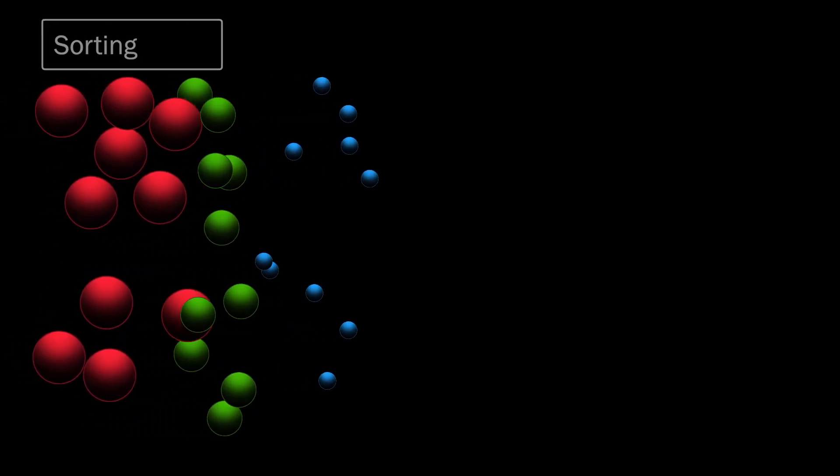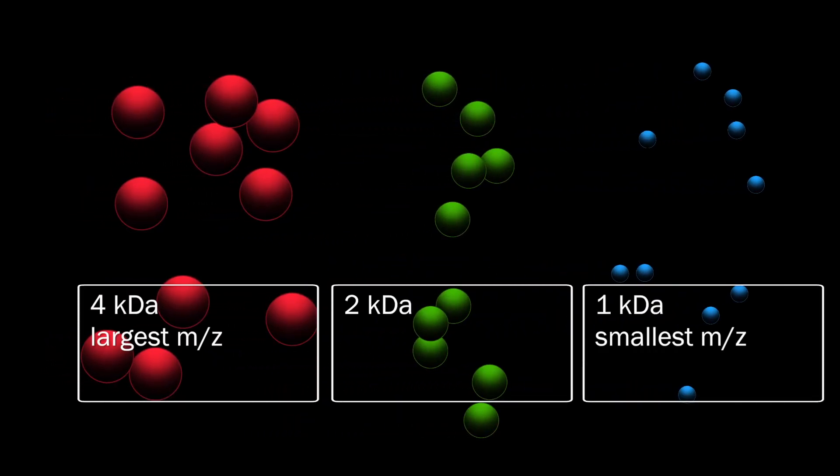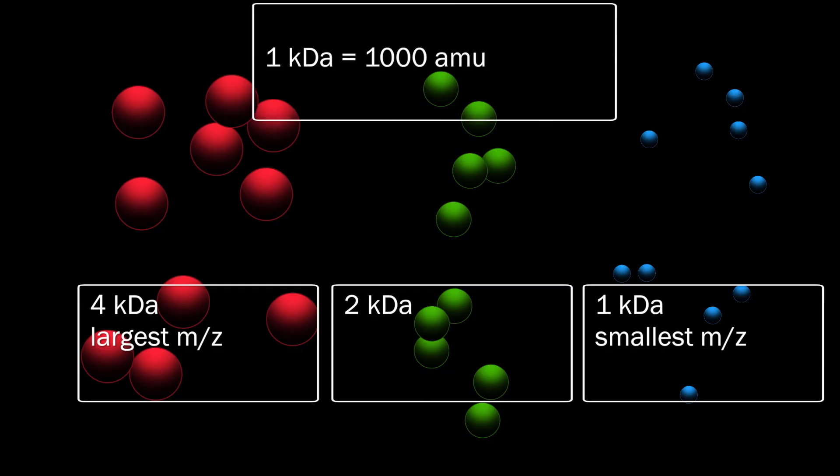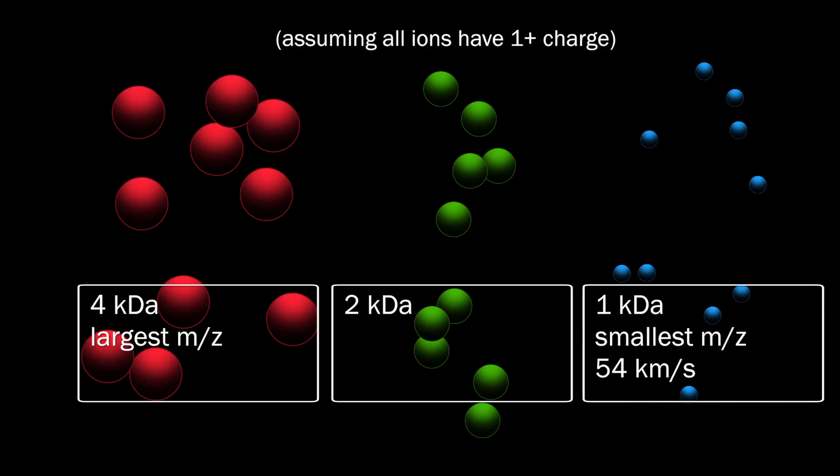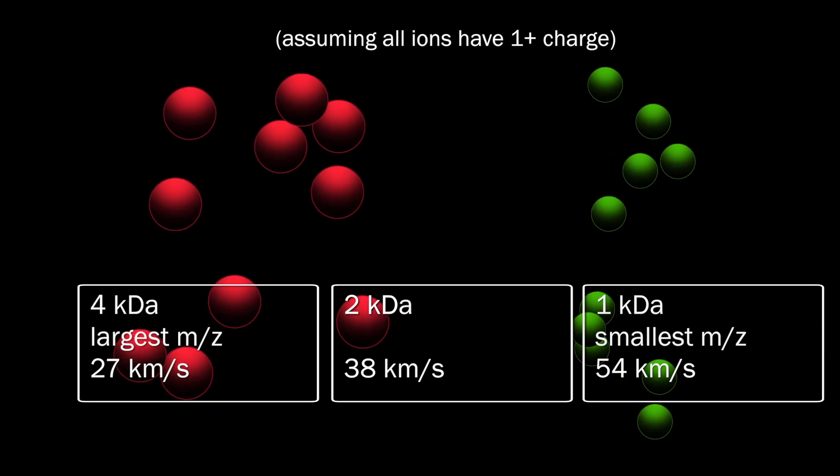In this example, we have a mixture of three macromolecules with masses of 1, 2, and 4 kilodaltons, where 1 kilodalton equals 1,000 atomic mass units. Using standard TOF conditions, this would cause the smaller 1 kilodalton ion to be accelerated to the fastest velocity, around 54 km per second. The 2 kilodalton ion would be accelerated to around 38 km per second, and the largest 4 kilodalton ion would be accelerated to the slowest velocity, around 27 km per second.